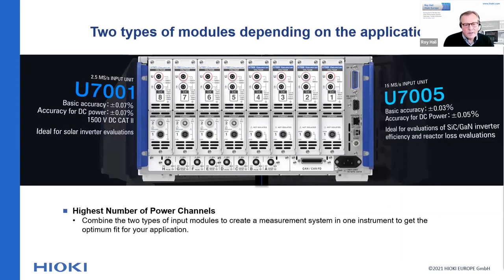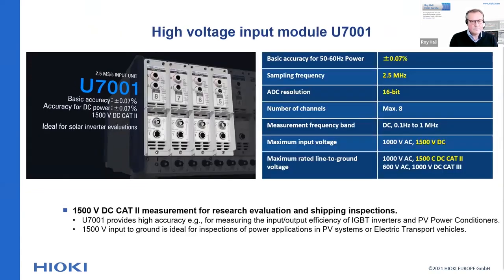As I mentioned earlier, there are 2 different input modules available: the U7001 high voltage input unit and the U7005 high accuracy input unit. You can freely select them and combine them in any order in the PW8001. If we take a closer look at the U7001 input unit, we see that it can measure up to 1500 volt DC in a Cat2 environment.